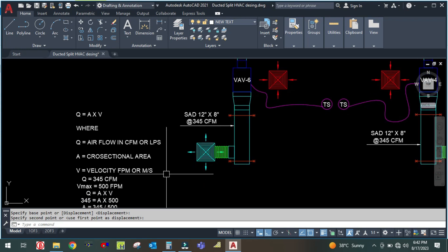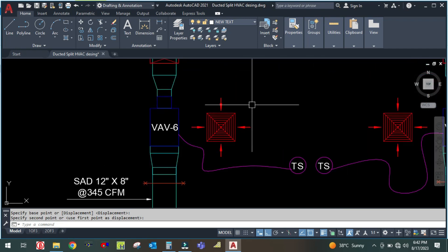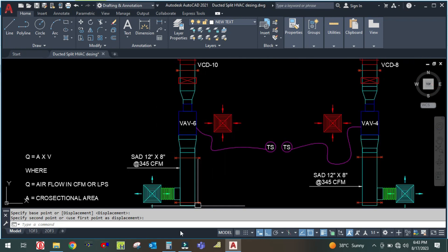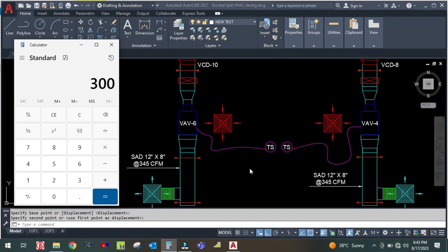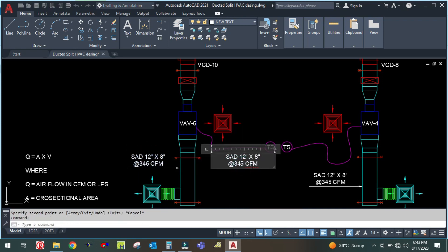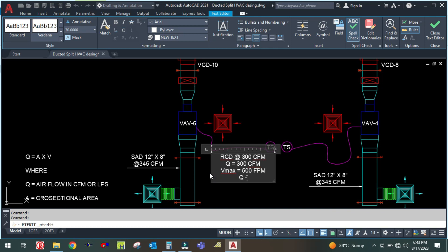Similarly, you can calculate for the return diffuser as well. For example, the return diffuser CFM is 300. So Q is equal to 300 CFM for the return ceiling diffuser. V max is equal to 500 feet per minute.